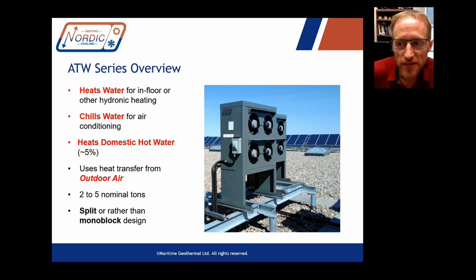Just the basics first, I guess. The ATW series can heat water for in-floor heating or other hydronic heating, and chill water in the summer. Because we have a split system, we can have a desuperheater to heat domestic water. That's a feature which uses about 5% of the unit's capacity while it's running for space heating or cooling purposes, and directs that capacity toward a domestic hot water tank through a double wall heat exchanger. Of course, it uses heat transfer from the outdoor air, so it's always exchanging heat with the outdoor air, no matter which mode it's in.